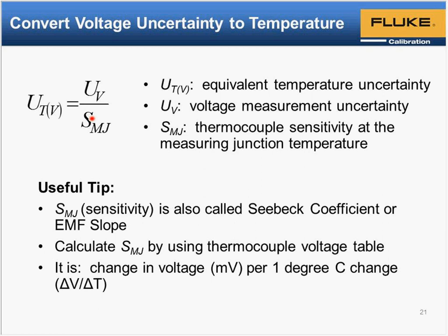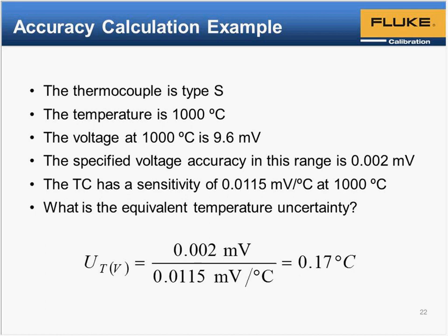value, if you don't know what it is for your thermocouple, well, first let me say you need to know what it is at the temperature that you are measuring, because it does vary depending on the temperature. So the easiest way to find out what it is, you just look at a typical thermocouple table like the one found in the ASTM book or on the NIST website, and all you have to do is calculate the change in voltage over a 1 degree Celsius change. And usually tables are already set up in increments, so it makes it really easy. You just look at the two adjoining voltage values at the temperature that you are working with and calculate the change in voltage, and that way you get voltage over change in temperature, or over a 1 degree Celsius change in temperature. Okay, here's an example. A test thermocouple that's being measured at 1000 degrees C. And the meter that we're using has a specified voltage accuracy of 0.002 millivolts.